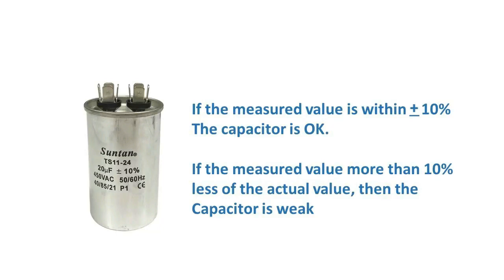If the observed value is less or more than 10% of the capacitor's original value, the capacitor is weak or defective. If we use this capacitor with the motor, the current drawn by the motor will be increased and the motor winding will get overheated.